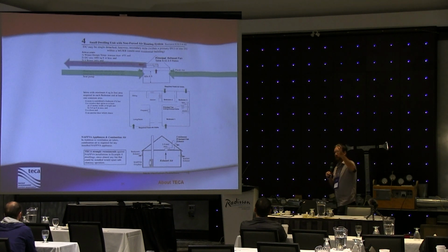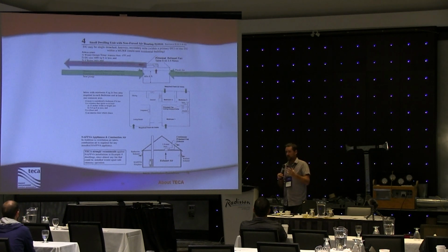It's very critical that you choose these locations wisely, namely because on most of the systems that I've seen installed, when we go back for service at a later date, you see a lot of duct tape taped over these fresh air inlets because people don't like the draft. So you really have to watch for that. What they've done is they've totally shut their ventilation system down as soon as they do that. So these systems are really subject to being disrupted and not providing the ventilation that they're intended for. So it is very important that the installer pay close attention to the location of these fresh air inlets.